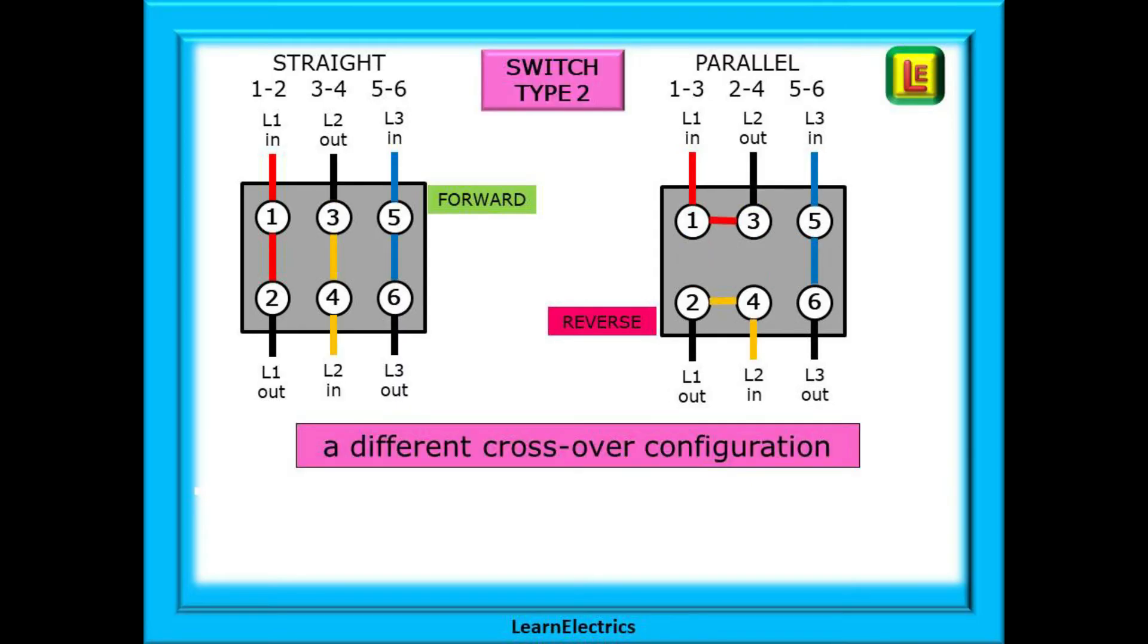Type 2 switches work differently. They have straight through connections as before, but the changeover of two phases is done by a parallel change, not a crossover. 1 goes to 3 and 2 goes to 4, and this time in our example 5 and 6 remain as a straight through connection.